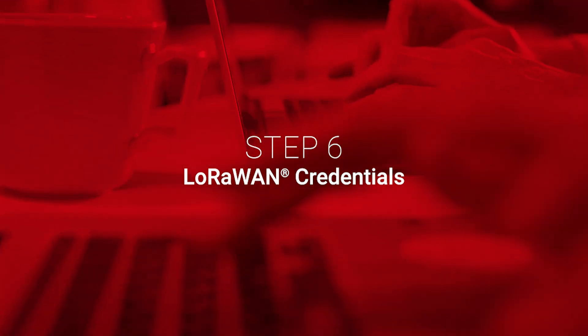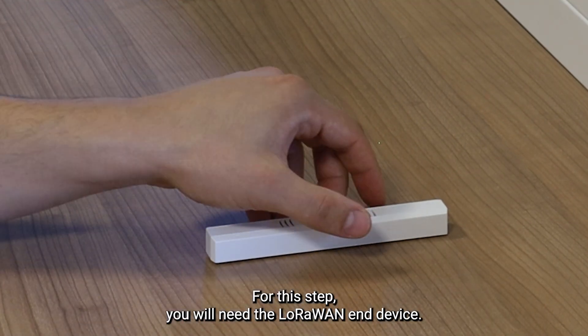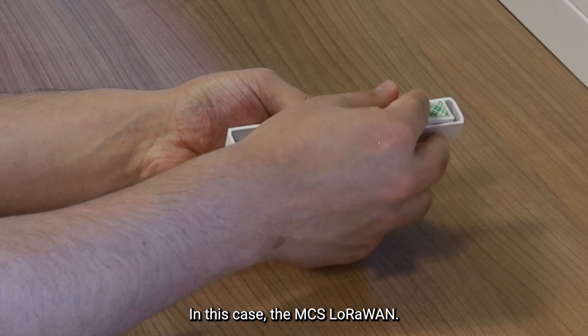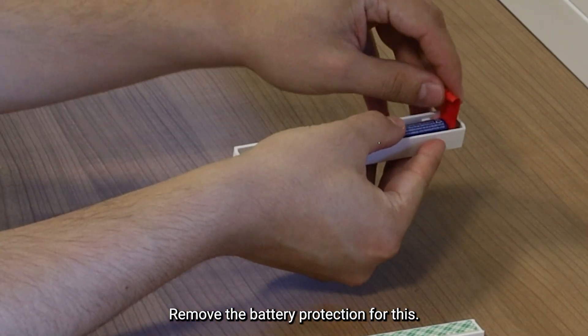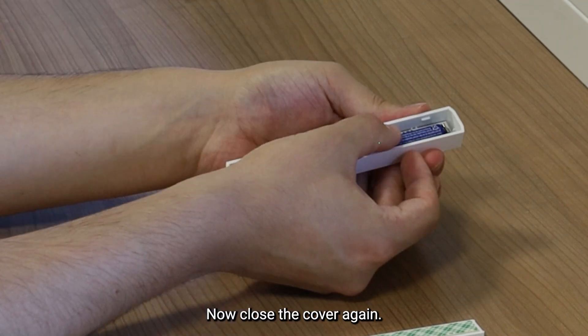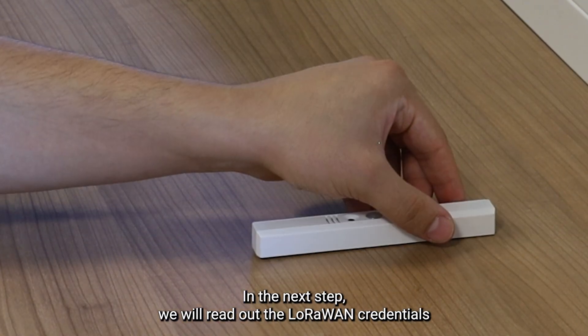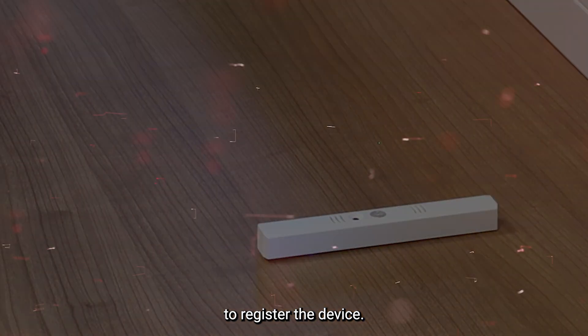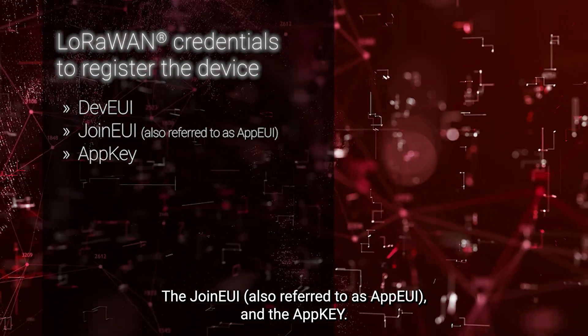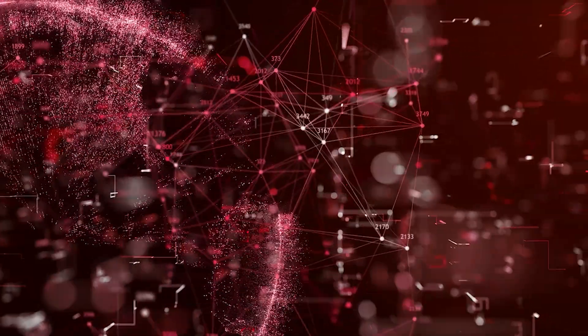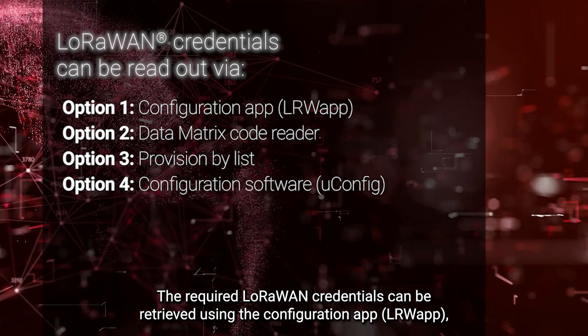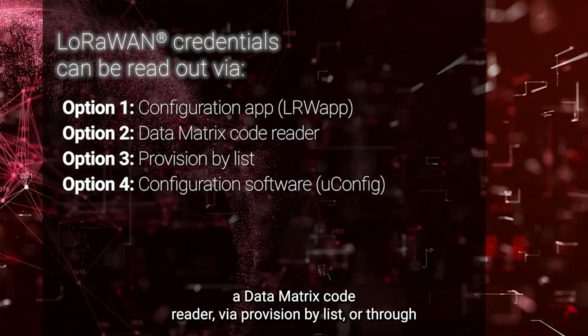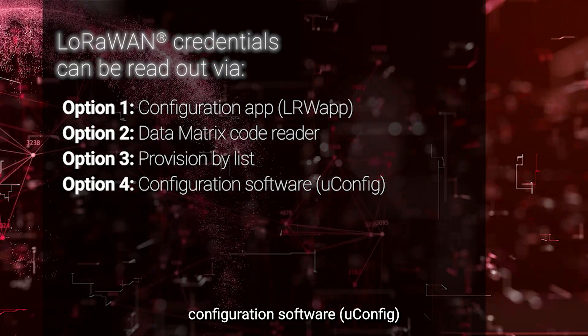Step 6. LoRaWAN credentials. For this step, you will need the LoRaWAN device. In this case, the MCS LoRaWAN. Insert the battery into the device. Remove the battery protection for this. Now, close the cover again. In the next step, we will read out the LoRaWAN credentials to register the device. For this, we need the DevEUI, the JoinEUI also referred to as AppEUI, and the AppKey. The required LoRaWAN credentials can be retrieved using the configuration app LRWApp, a data matrix code reader, via provision by list, or through configuration software uConfig.